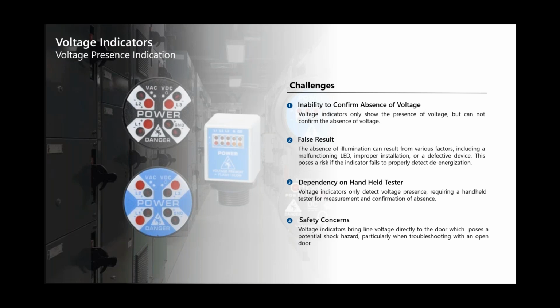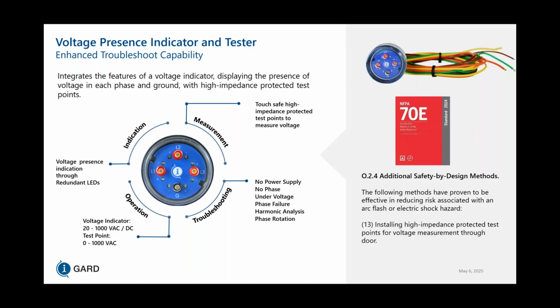There's a safety concern as well. Voltage indicators bring line voltage directly to the door, which poses a potential shock hazard, particularly when troubleshooting with an open door. Now, voltage test ports integrate the features of a voltage indicator and also have high impedance protected test points. The voltage presence is indicated through redundant LEDs, 2 per phase and 2 for ground. And we also have high impedance protected test points to measure voltage. Although the voltage seen on the bus is appearing at the door, the impedance path is really high, and therefore the current level is very low.